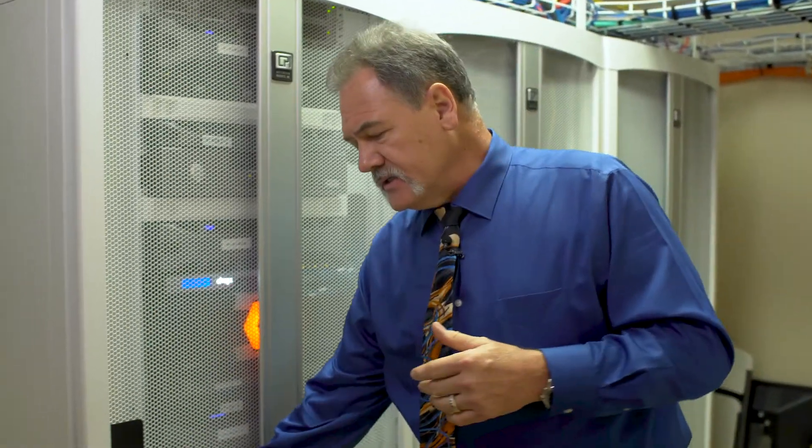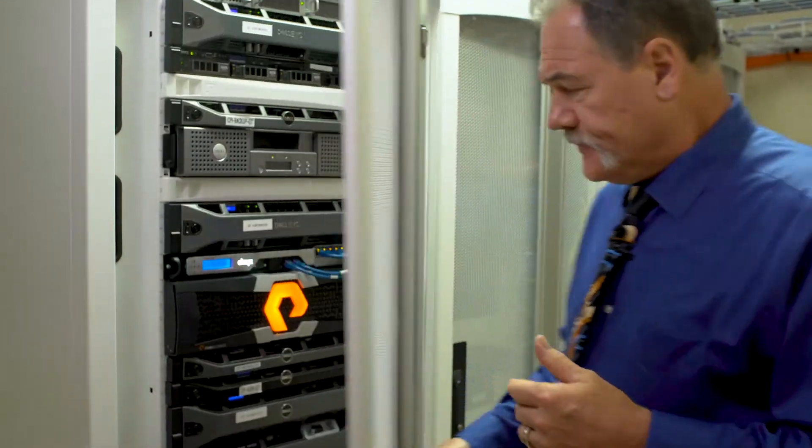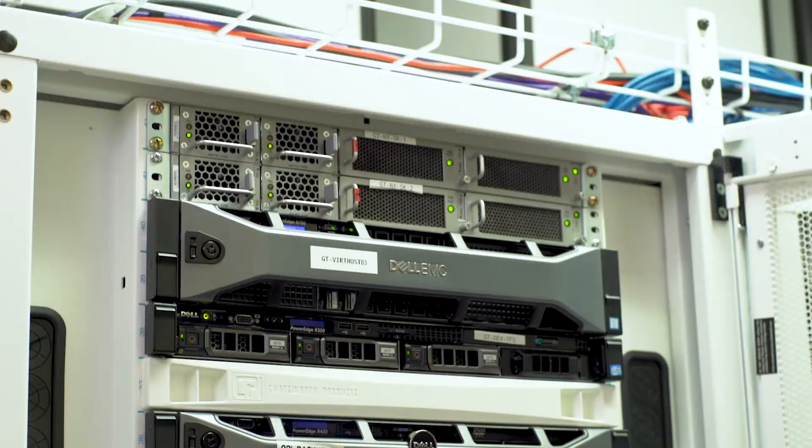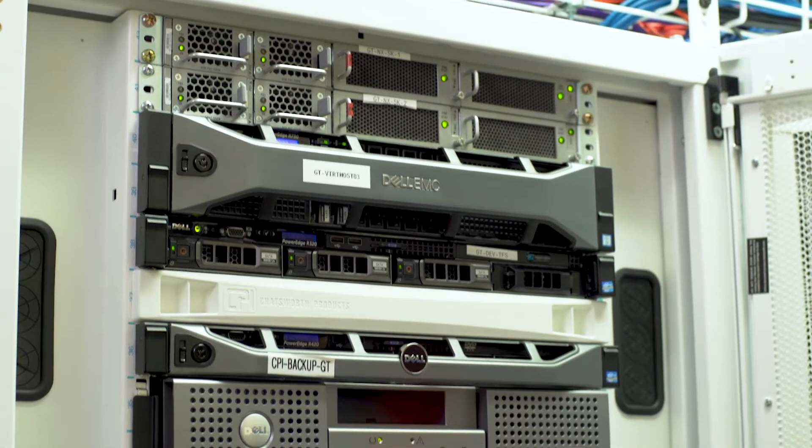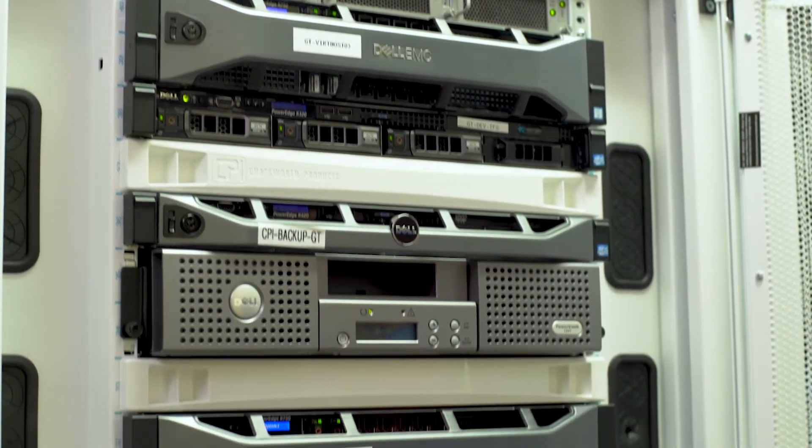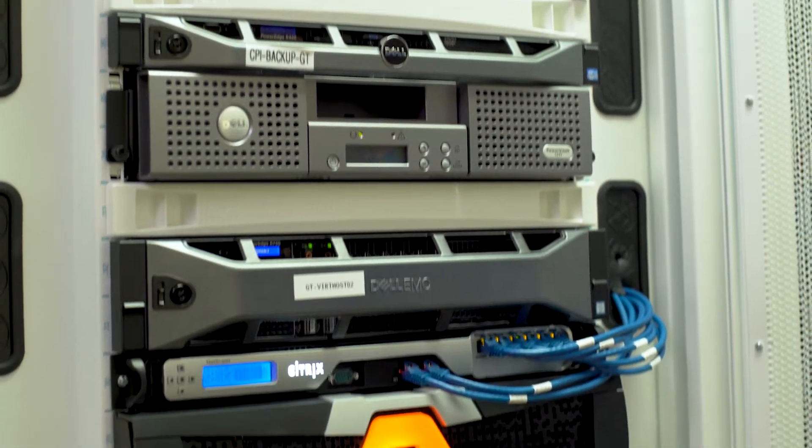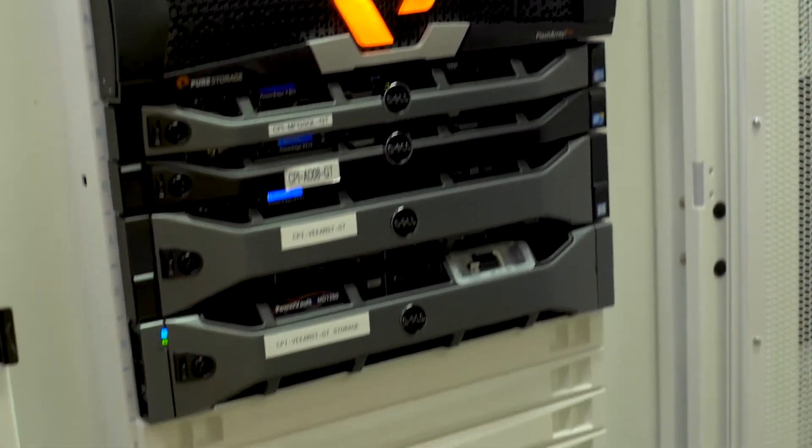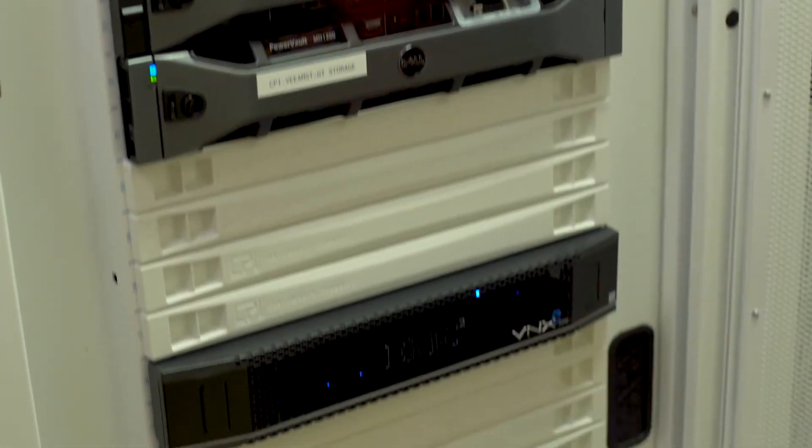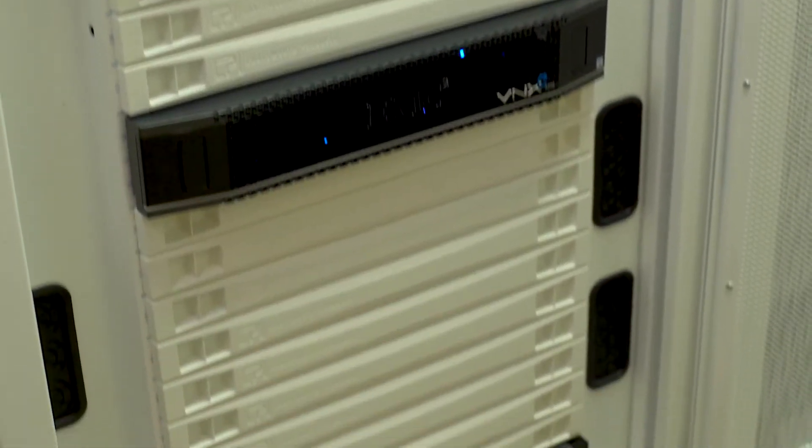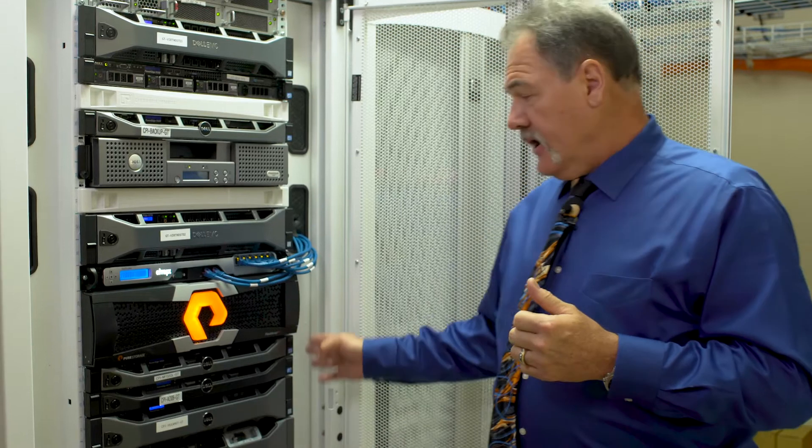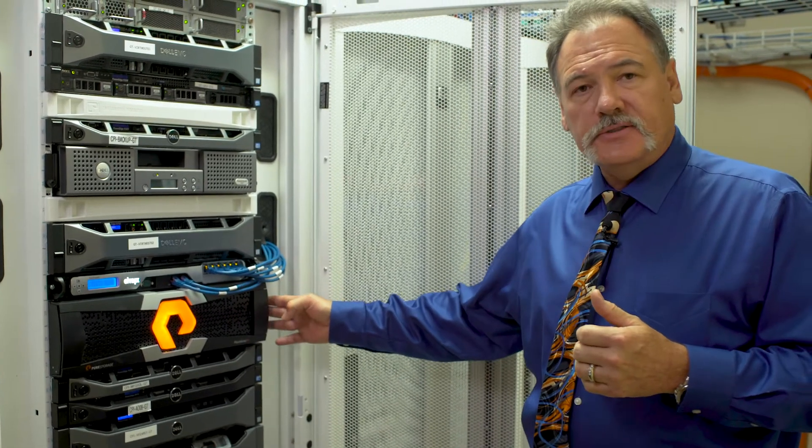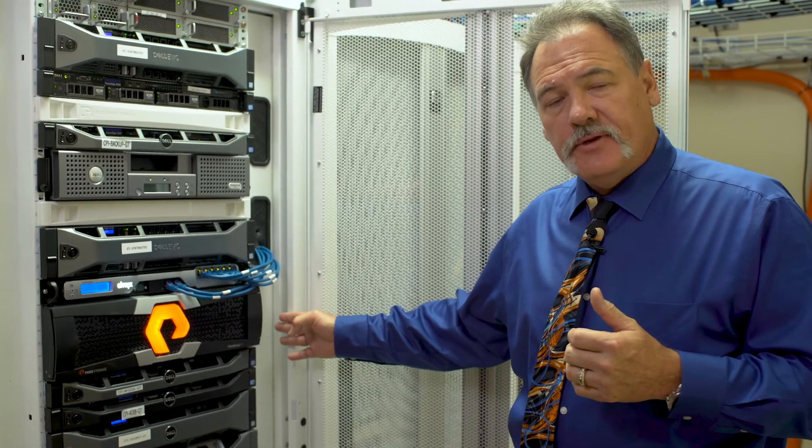So in this cabinet as you look through it you will see where all the open slots are sealed. We don't have any blanks that are open. Everything is completely sealed on the front. On our sides from our side rail to the side of the cabinet everything's blanked off.